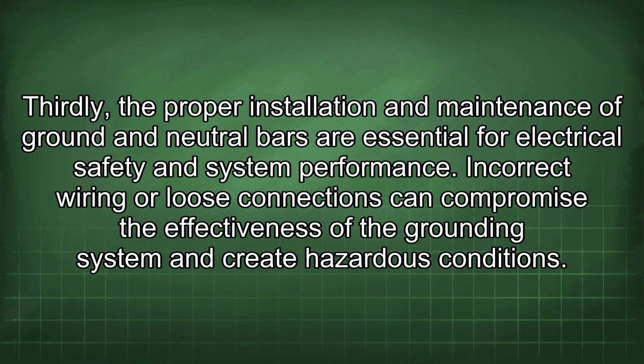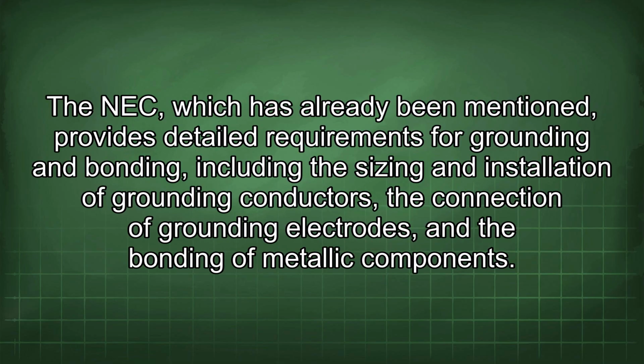Thirdly, the proper installation and maintenance of ground and neutral bars are essential for electrical safety and system performance. Incorrect wiring or loose connections can compromise the effectiveness of the grounding system and create hazardous conditions. The NEC, which has already been mentioned, provides detailed requirements for grounding and bonding, including the sizing and installation of grounding conductors, the connection of grounding electrodes, and the bonding of metallic components.